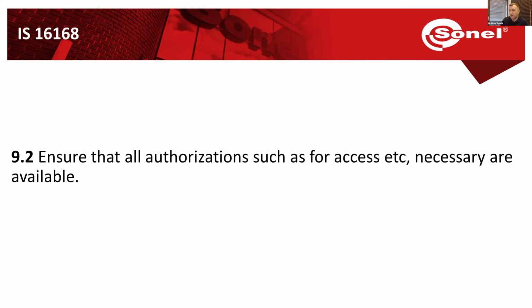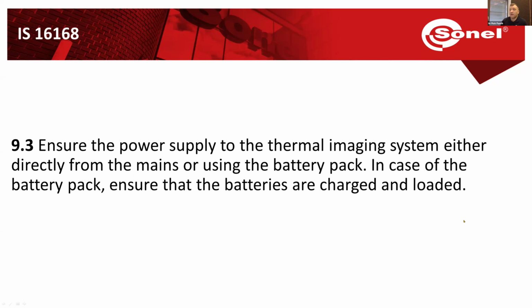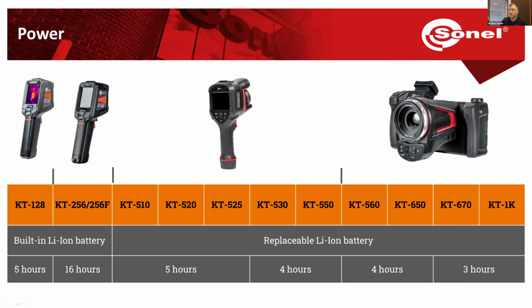For example, we need to be authorized to access a transformer station or a distribution substation. Then we need to make sure we have the right power supply to our thermal imaging camera. The standard gives some options: from the mains or from batteries. At Sonel, our cameras are powered with batteries. The lower models have a built-in battery, but it lasts a long time, up to 16 hours, which is pretty good.